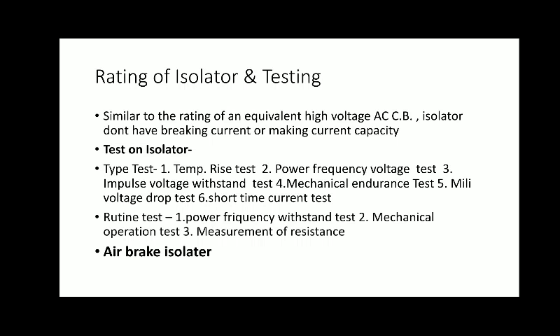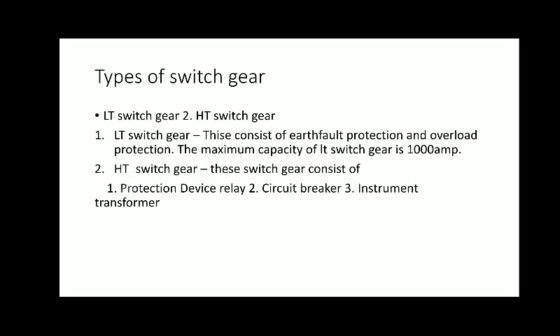Their purpose is to ensure proper forcing on the isolator movement in opening the switch, and then a smoothing action after the circuit has broken, or the forcing action in the first movement of closing, and a smoothing action as it is closed. It is essential that all the springs are similarly adjusted during the making and breaking. So after that, types of switchgear.